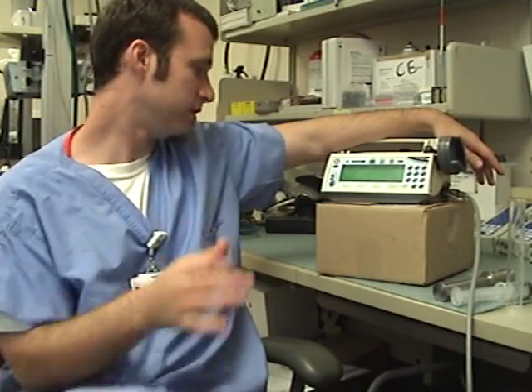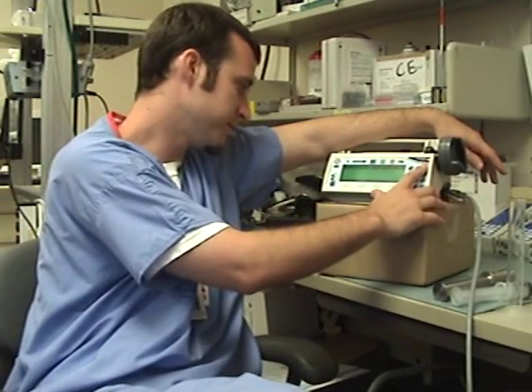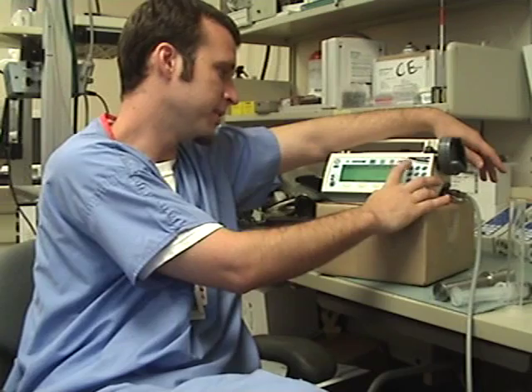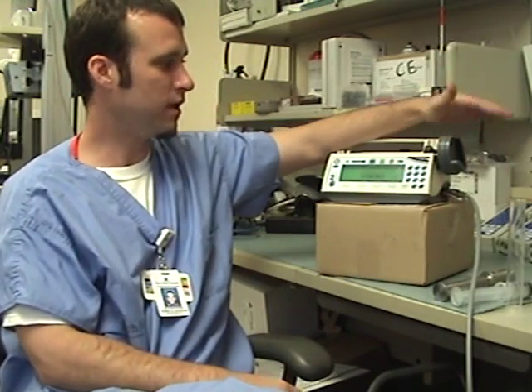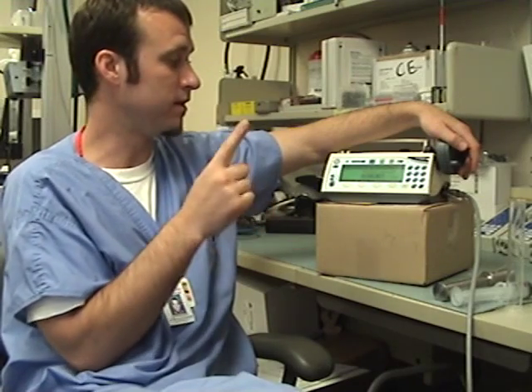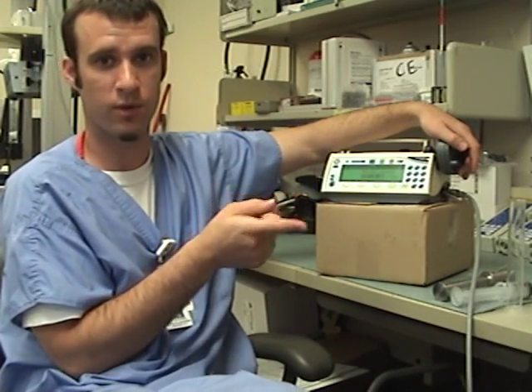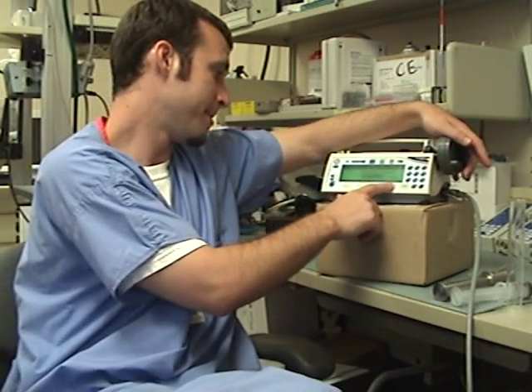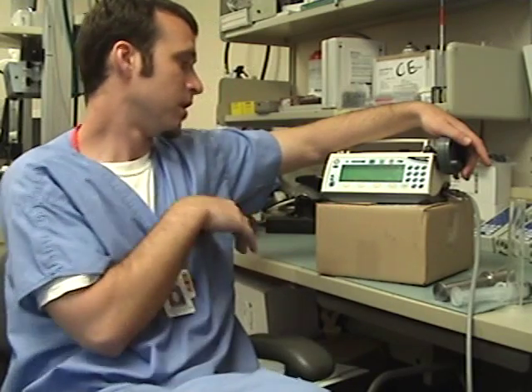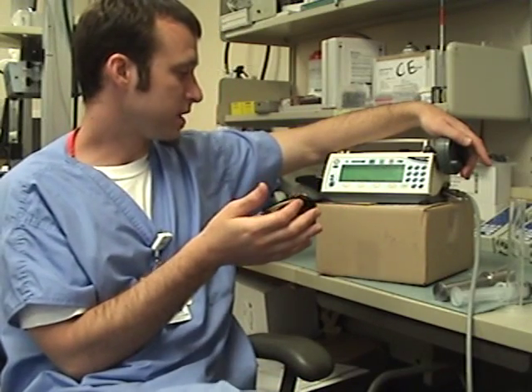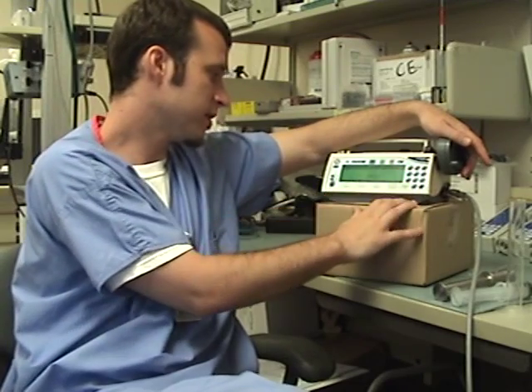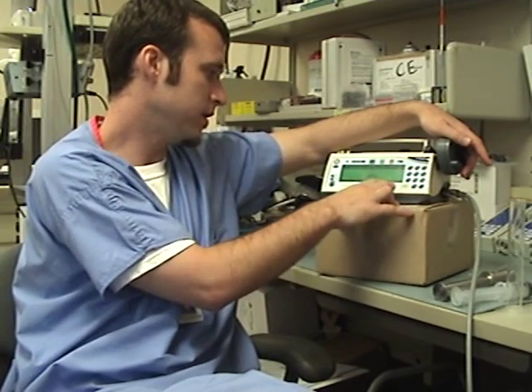From here, you're going to want to go into the utilities section and set and view the last PM date. The unit is internally timed so that after 1 year, if preventive maintenance hasn't been done, 30 days after that date ends, then the unit will alarm and say maintenance required, and you have to go and reset the PM date when you do the PM. Next, you're going to want to check and make sure that the time and date inside the unit are properly set, which is good here.